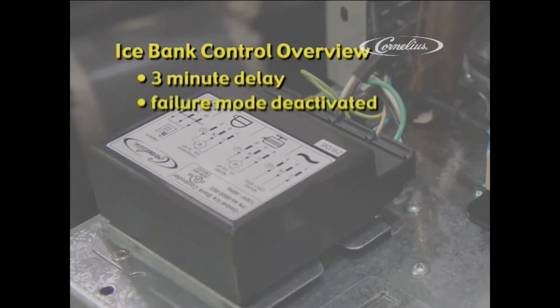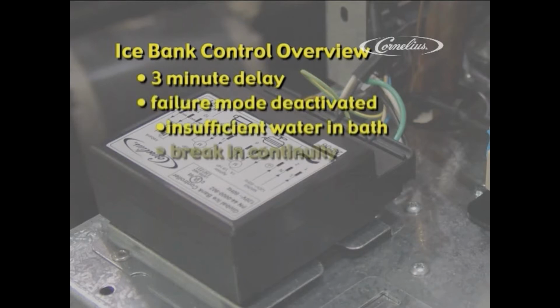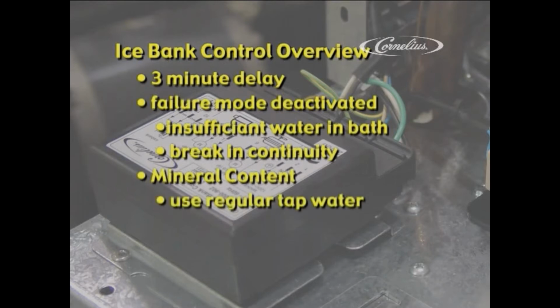The IBC failure mode is deactivated if there is no or not enough water in the water bath to cover the probe assembly, or if there is a break in the continuity, as in a broken wire or connector, the control will not activate. Be sure when filling the water bath that the mineral content in the water is sufficient. It is suggested that regular tap water be used. Distilled or some bottled waters have the minerals removed to the point that the controls cannot sense them and therefore will remain in the deactivated state.